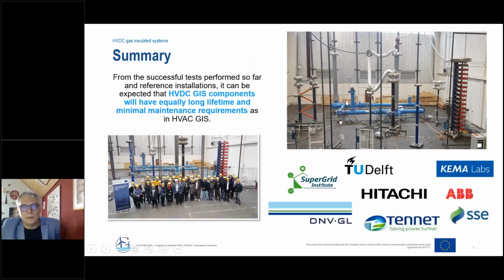Let me start directly with a summary of one of the main targets of work package 15 we have reached in the past. You can see here on the right side a test setup of a gas insulated switchgear for HVDC rated for 320 up to 350 kV. That was one of our main targets, to increase the technology readiness level for a gas insulated HVDC switchgear.